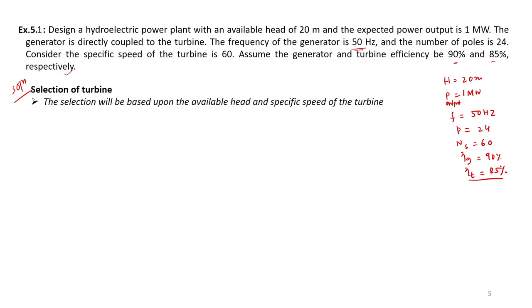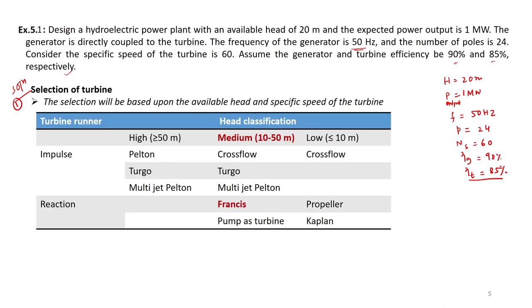Before designing, let us go for selection of the turbine. The selection will be based upon the available head and specific speed. If we classify with respect to head: high head is more than 50 meters, medium head is 10 to 50 meters, and low head is less than 10 meters. In our case, the head is 20 meters, so it falls under medium head.